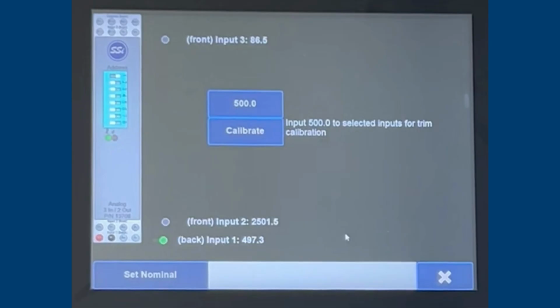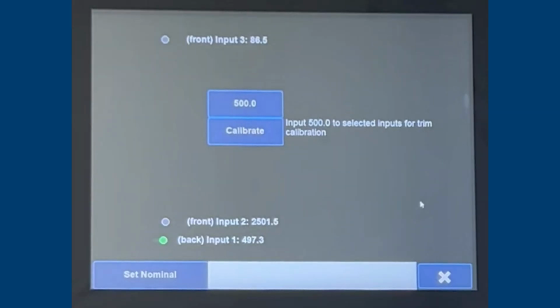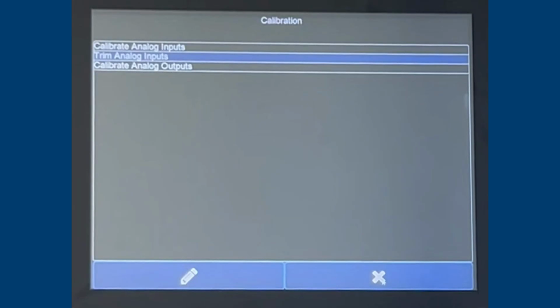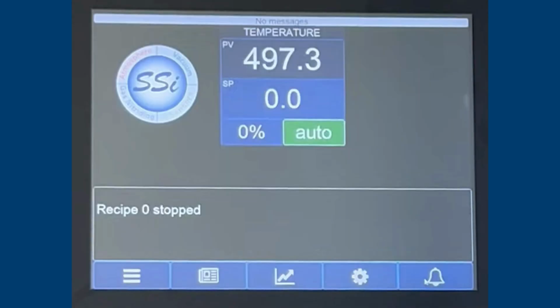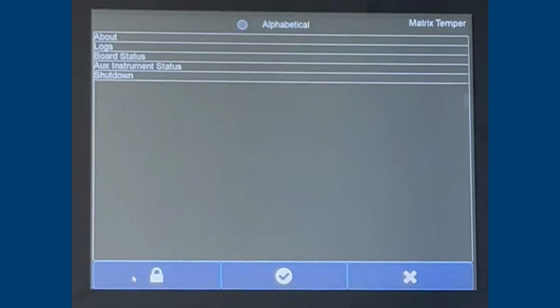Once you are satisfied with the zero and span, as well as trim, you would then select the X to close out the calibration process. Hit the X to return to the main menu and the X to return to the main screen. You can check your temperature being sourced in either at your PV, or if you have more than one module, you can check the board status and this will tell you each input and how they are reading.